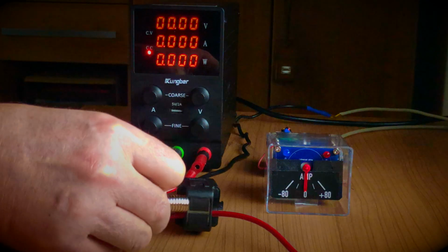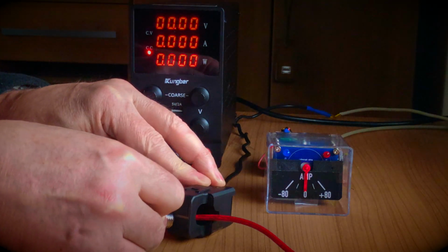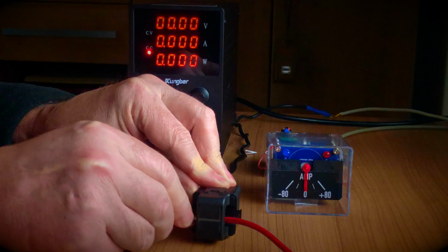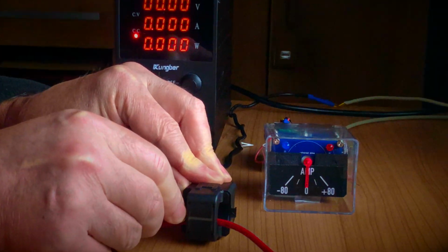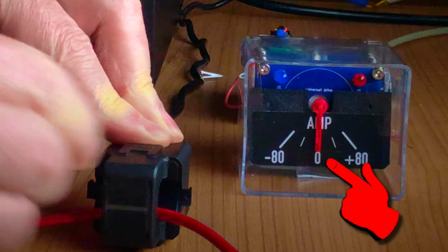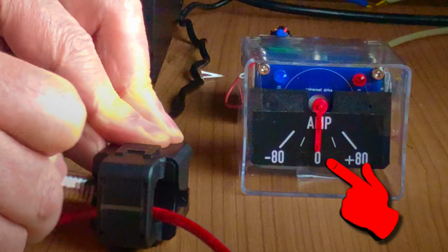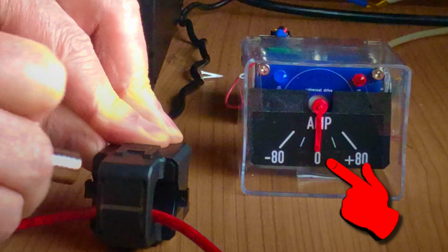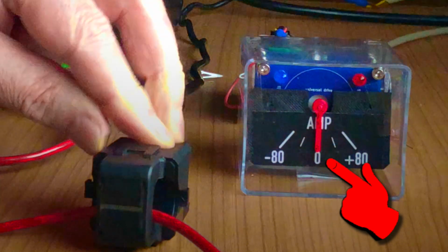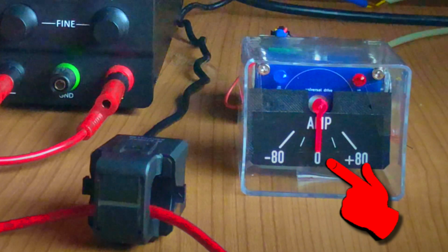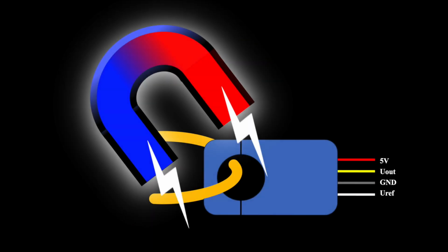The experiment with a strong neodymium magnet is giving us an estimate whether this is a critical issue. Surprisingly, I can hardly produce any deviation with the magnet, even if I get very close to the sensor. In that experiment, the deviation caused is a single-digit percentage only. Nevertheless, don't place the sensor near devices generating magnetic fields. Better keep it at least 10 centimeters away from electric motors, relays and the like.